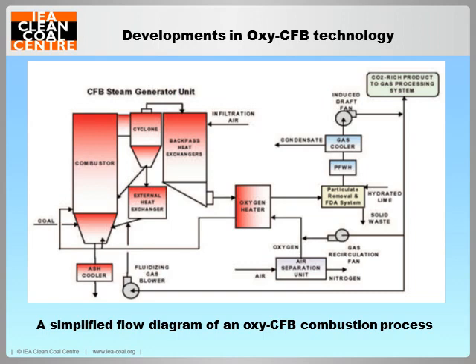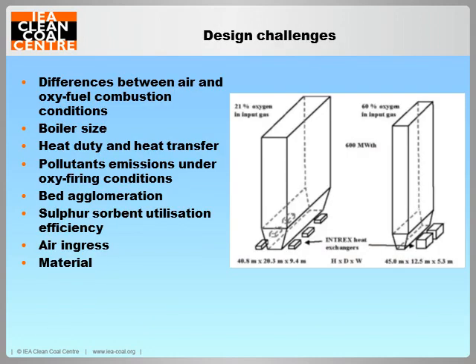Oxy-fuel combustion is one of the main options for CO2 capture from combustion plants. This figure shows a simplified process flow of the Oxy-CFB combustion plant. It consists of the air separation unit, an Oxy-CFB power generating plant, and a CO2 treatment unit. In principle, normal CFBC boiler designs with reasonable modification can be applied for Oxy-CFB boilers. However, there are several challenges in designing Oxy-CFB boilers.